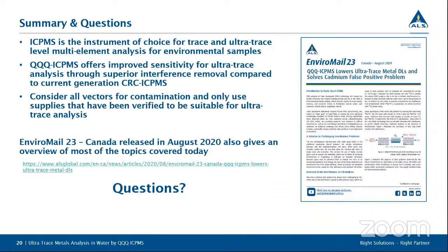The only real benefit that the triple quad will give you is if you have a specific interference that you're trying to remove, and then, as I said, the triple quad can remove a double charge interference for some analytes, which the regular collision cell can't. But I would say that the regular collision cells are probably going to be the standard for quite some time.